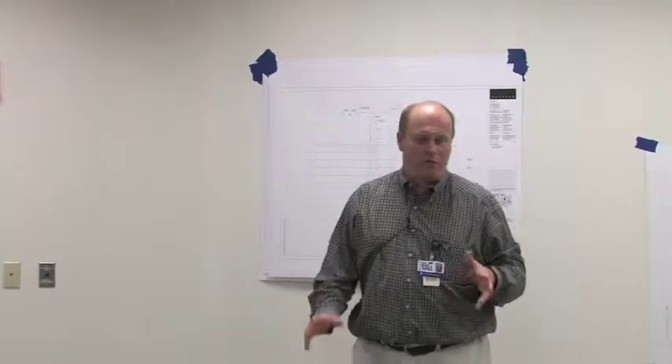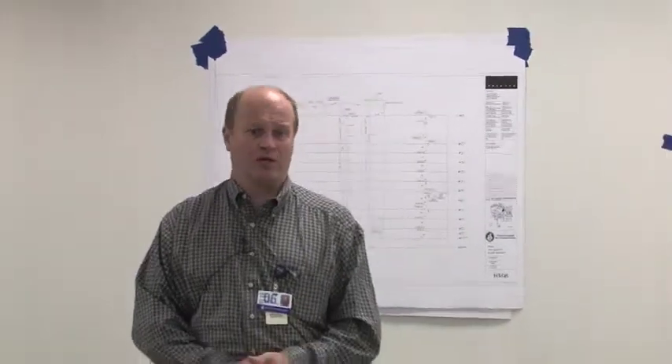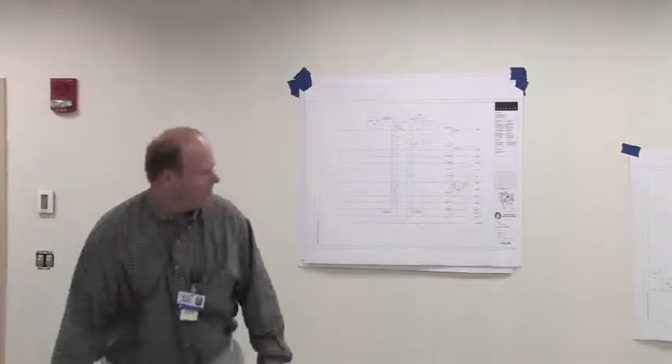Question: Is that 30,000 gallons still 96 hours worth of fuel? Answer: Yes — that's calculated with all four generators firing at full load. Currently, your emergency loads here would probably run about two and a half machines. We sized it as all four running, so in reality you could run much longer supporting the building's life safety and selected emergency loads during a prolonged event like Hurricane Sandy.